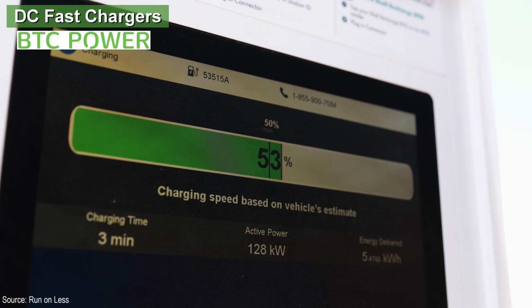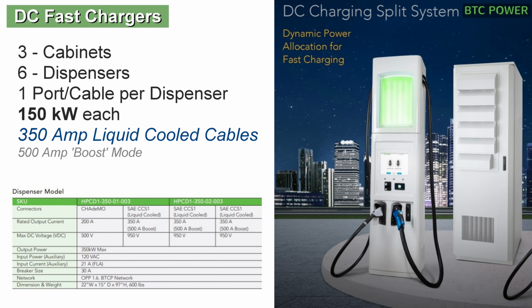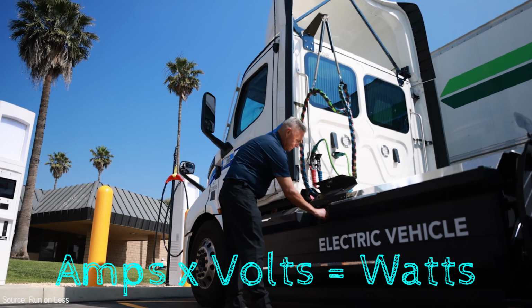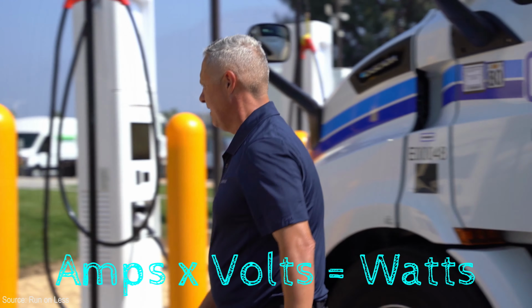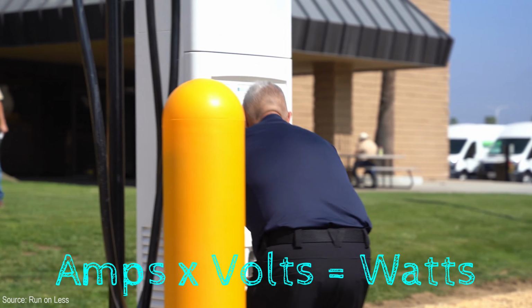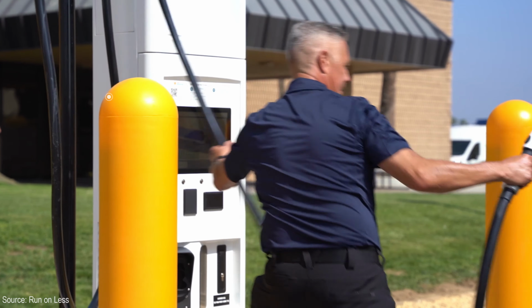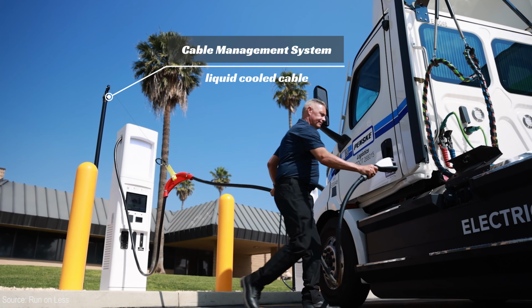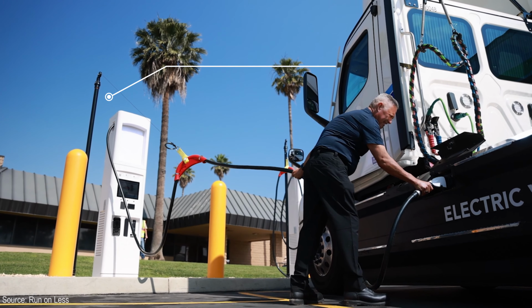There are lots of factors that affect charging speed. This is a dispenser fed by a separate cabinet. From the spec sheet, given that these are rated at 150 kilowatts, they must be using the liquid-cooled optional cable rated at 350 amps, but they say you can boost that to 500 amps for short periods of time. Amps times volts equals watts or kilowatts, and because these are big trucks, they have long cables that need cable management systems to keep everything tidy.